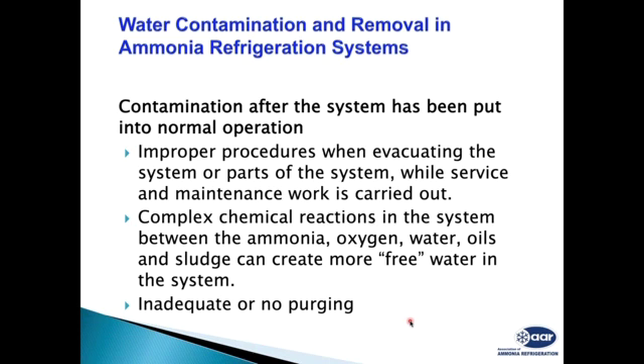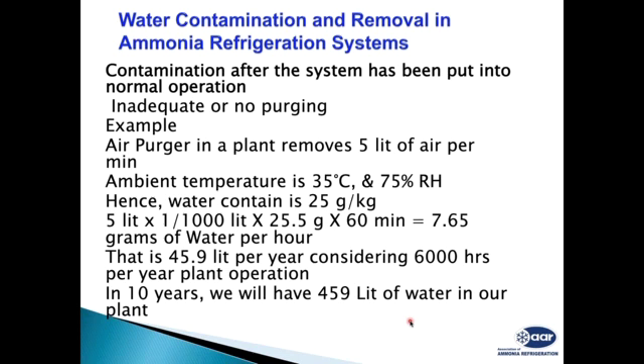Next, we'll see how it happens. This is a typical example of water entering with the air. Let's say our system has an air purger. If we don't have an air purger, air will remain, and whatever water has come in will also remain in the system. Let's assume we have an air purger removing 5 liters of air per minute from the ammonia plant. The ambient temperature is 35 degrees centigrade with 75% RH, which is a typical coastal condition. At 35 degrees ambient temperature and 75% RH, the water content is about 25 grams per kg of air.